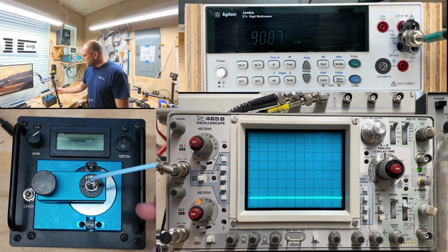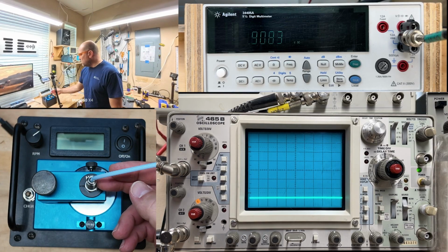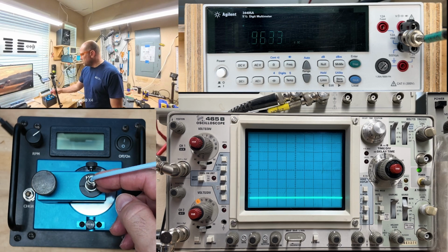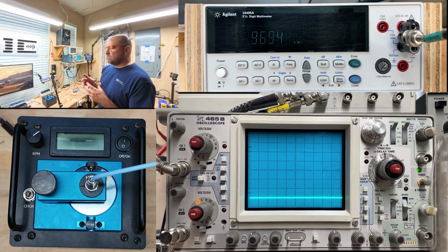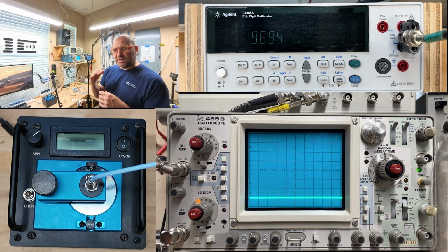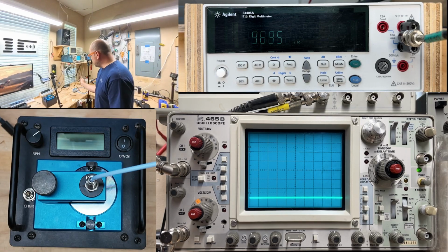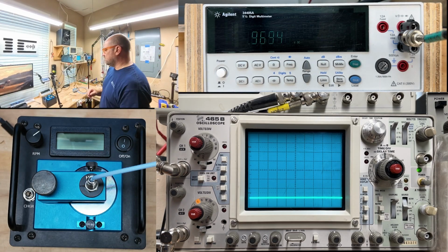You monitor it with a probe, like you would a steam turbine or a compressor with a proximity probe. We're going to intentionally be able to see what the oscillation looks like, or what the vibration looks like. So I have the proximitor output voltage connected to a digital multimeter, and also connected to this oscilloscope.